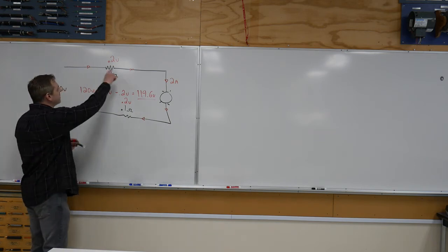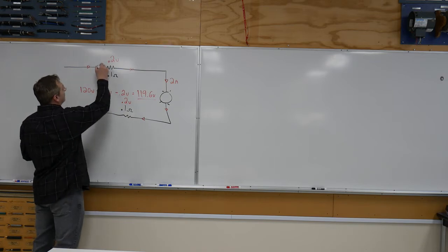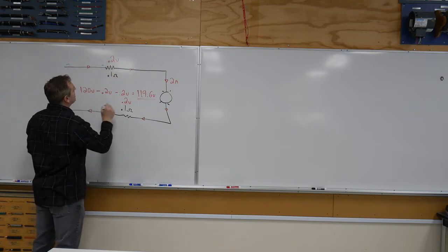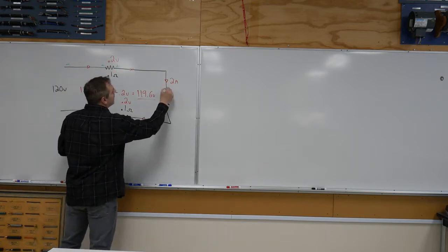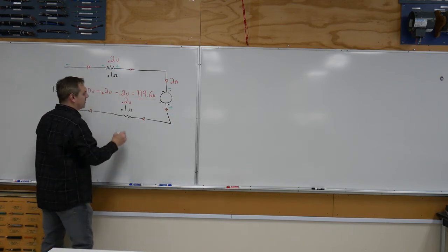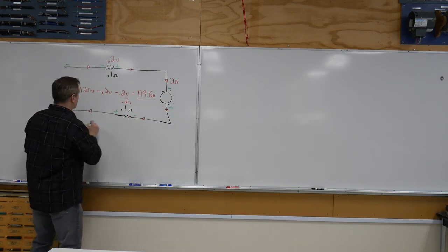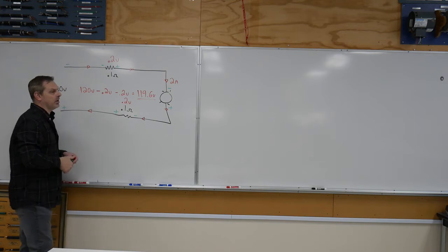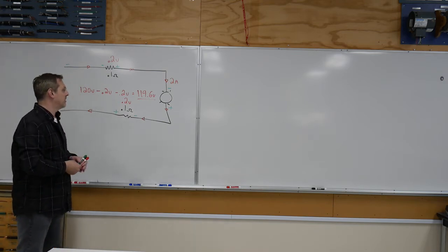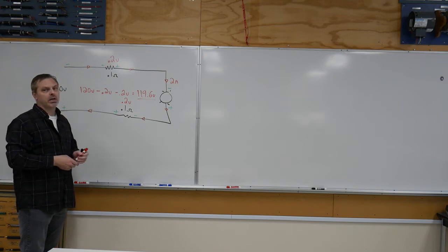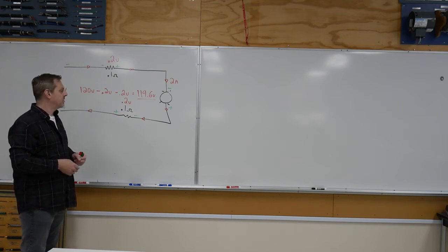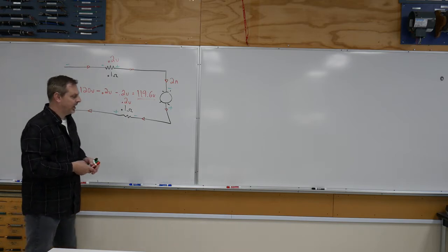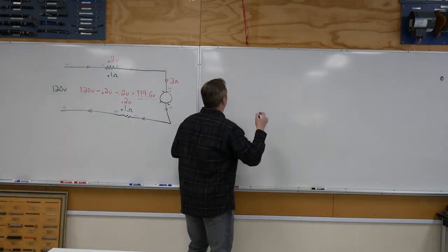All right, so that's pretty straightforward because that's just a line loss and line drop circuit. If we applied polarities to these resistors based on current flow, if we started up here, that's our true negative, so that's a negative there. Anytime we cross the load, we're going to get an instantaneous positive. This is negative, that's an instantaneous positive, instantaneous negative, and then there's our true positive heading back this way. So we have voltage drops that occur within here. Now you'll see when we add a three-wire circuit to this circumstance, sometimes the neutral contains what's called a voltage rise, and that's based on our polarity of our current flow on that neutral if it's an unbalanced three-wire. So let's explore one similar to that right now.